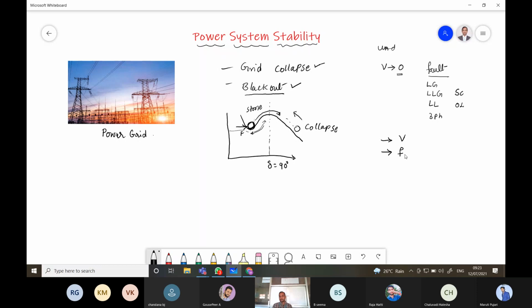The frequency of the generator and the bus bar or grid should be equal, and the phase sequence and terminal voltages should be the same. So these are the conditions. If any one of these conditions is not satisfied, the generator will come out of synchronization with the grid. So the generator falls out of synchronism because of a disturbance. We need to bring the generator back to the original, normal position. That is called stability.